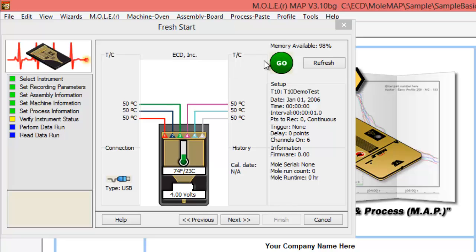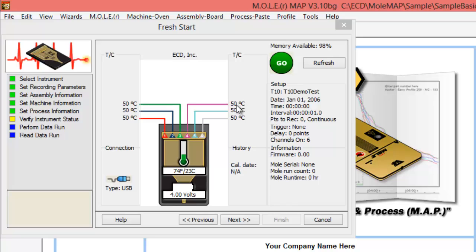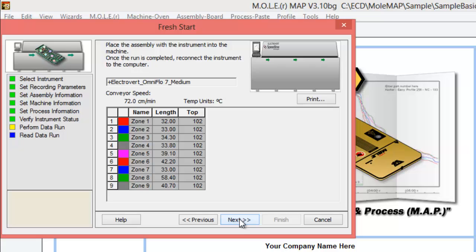You'll never get the go light if you have open thermocouples. So if it says stop here, don't be thrown off. It doesn't necessarily mean that something is amiss. It's basically letting you know that you have open thermocouples on your instrument status. So if everything else looks good to you.